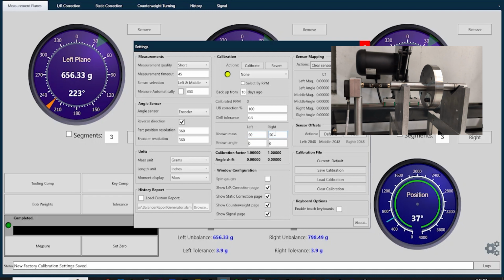If no number is written or you want to verify, you can remove one of the test weights and weigh it on a gram scale, then input the numbers into the box. Just below Known Mass, you will find another pair of boxes for Known Angle, which should both be set to 0. Once these numbers are entered correctly, press Calibrate above those boxes. Afterward, close the settings page.